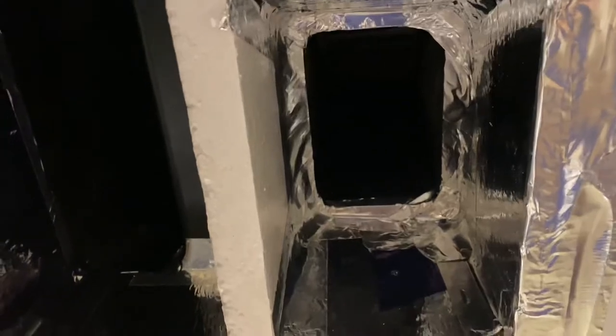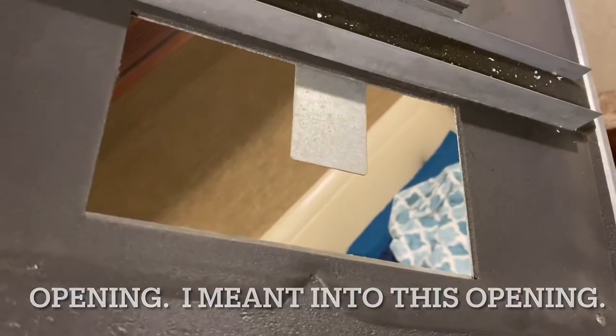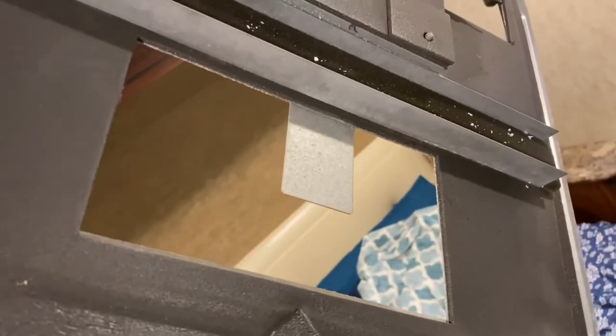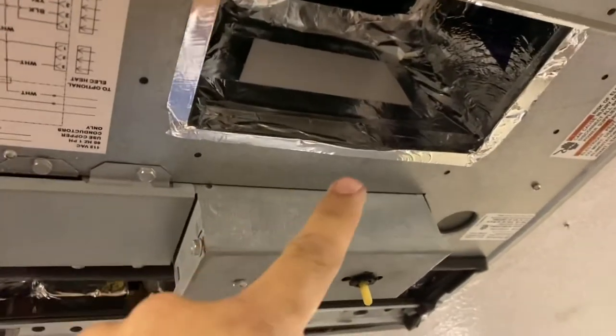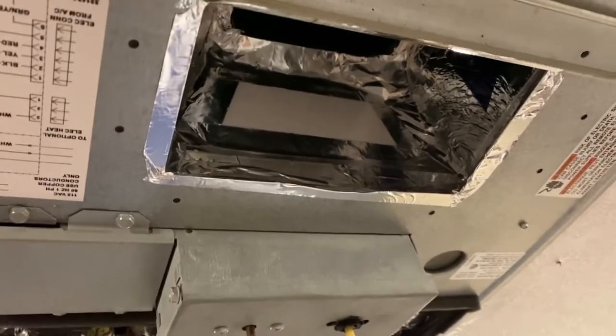This is what I came up with for my design to redirect this airflow. That's the return duct right there, and this is the duct that blows down into the room. I tried to make it so the air would come down directly as much as possible into this baffle right here. I'm probably going to see if I can cut this tab out as well because I don't see that it serves any purpose in this situation. So I'm going to get this plate screwed back up there and then use some tin snips to cut that little tab out in the middle.